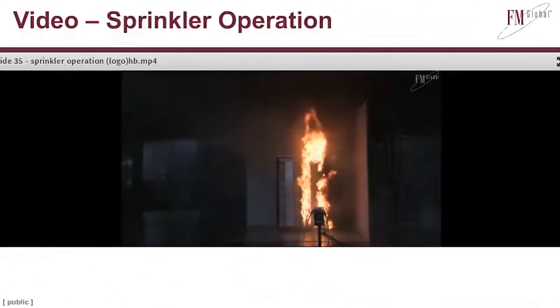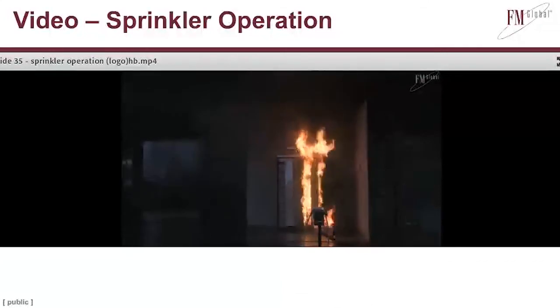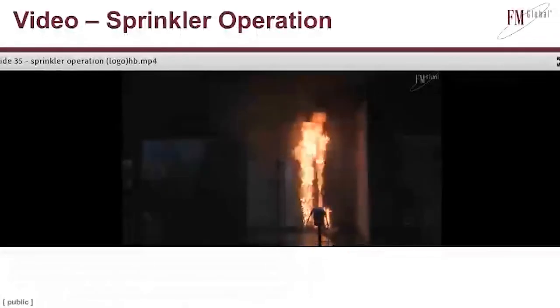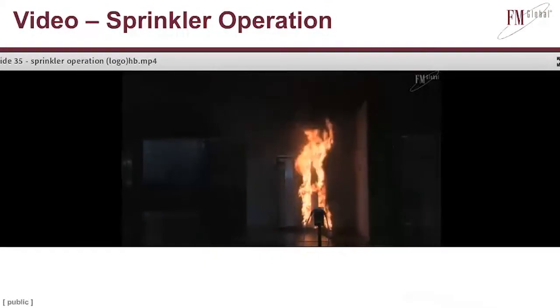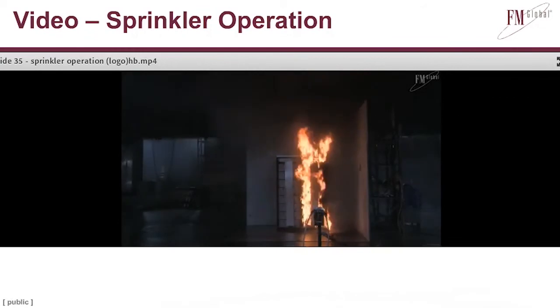If you consider that this energy storage system is inside a metal box, the only part open is the face, and the modules are spaced about 1/4 inch apart. So there's no real effective way for the sprinkler to put water inside this rack, and that would be necessary to suppress the fire. So the next thing it can do is control the fire, which means in this case, don't allow the fire to spread any further. So if you watch that target rack now, will the fire spread from what's burning now and then jump to that target rack and then generate a larger fire?